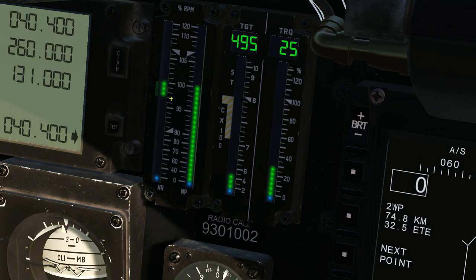However, these chiclets don't illuminate until that value is reached. So right now what you're really reading is less than 100%. Could be 99.9, but it's less than 100. So what I want to see once I set my rotor to 100% is one chiclet above 100, because that means I've reached 100 and it is somewhere between 100 and 101.